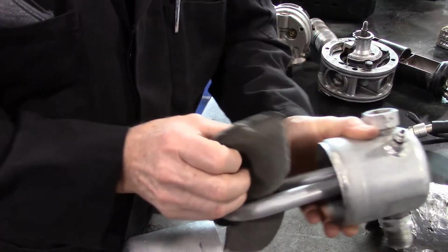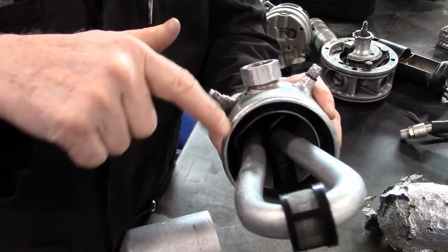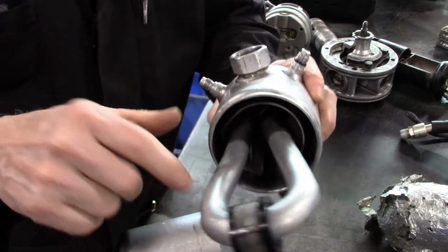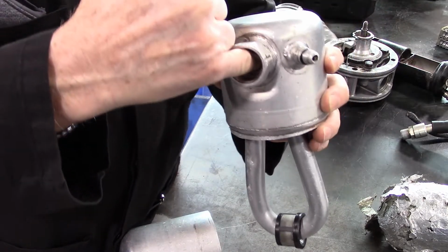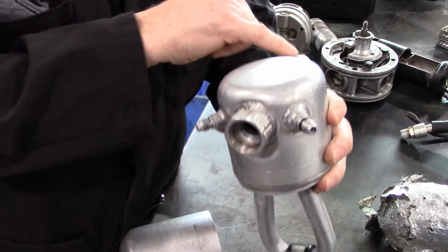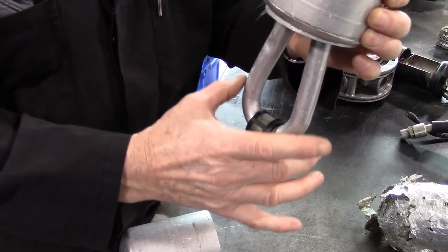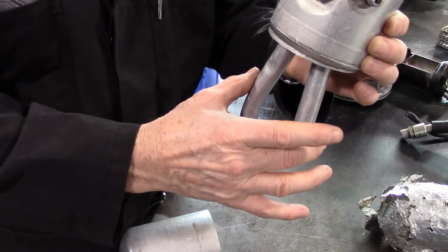Now the way that this works, I'm going to remove the desiccant, and it might be a little difficult to see, but this U-shaped pipe that's coming in here, the gas entering here, we don't want the gas to go straight through and out to the other side, so it hits the deflector. The deflector deflects the gas down to the bottom.